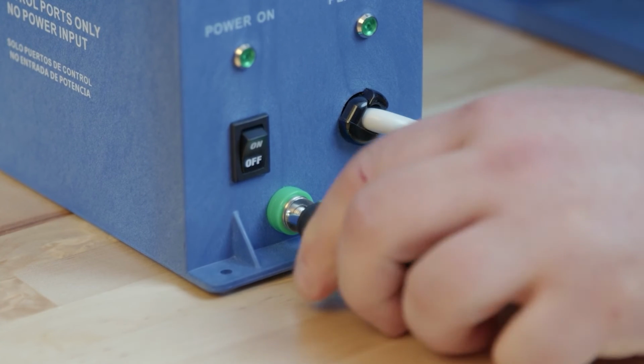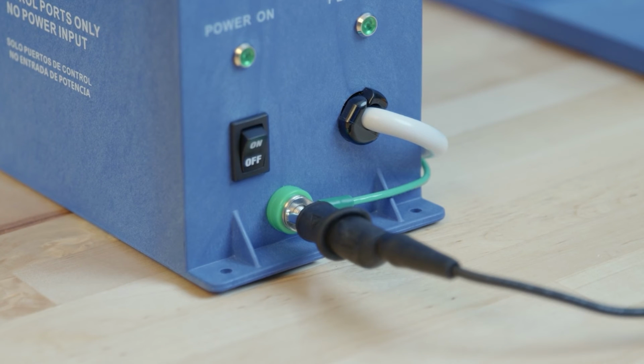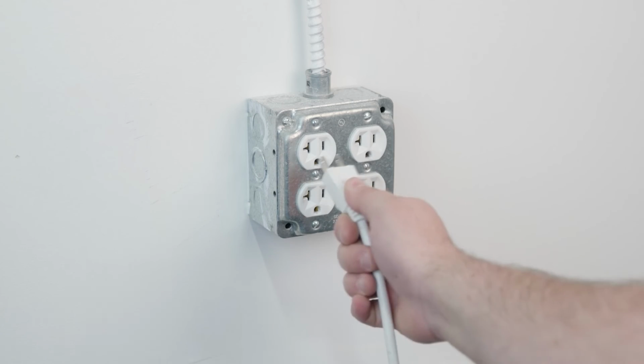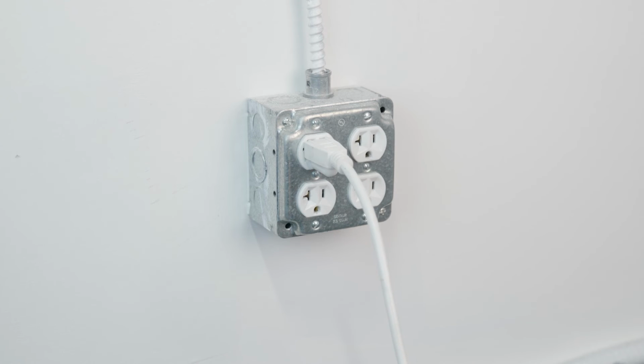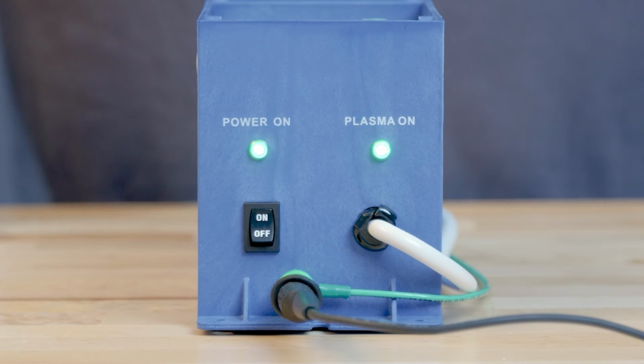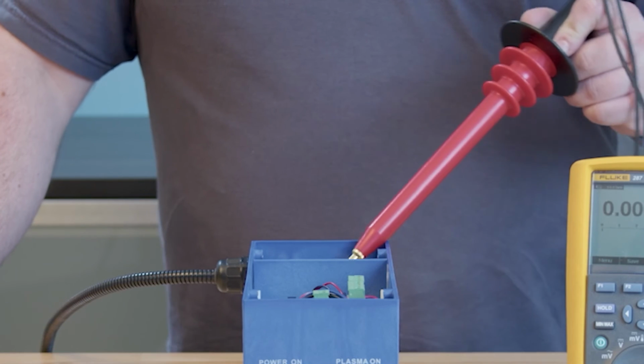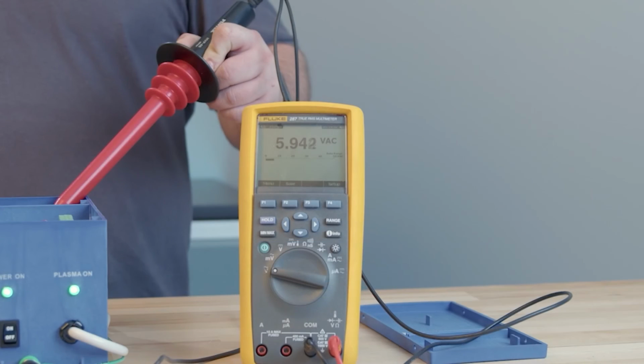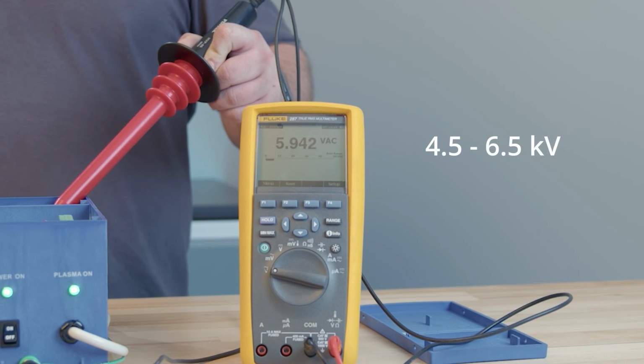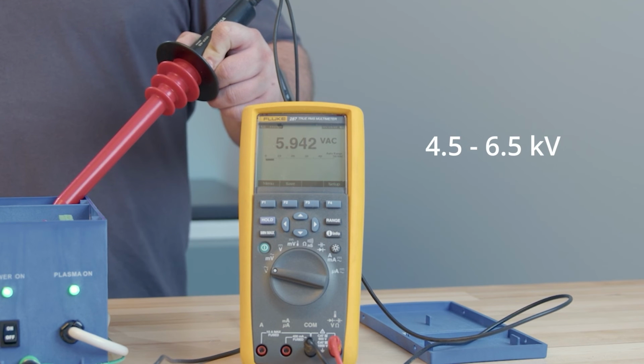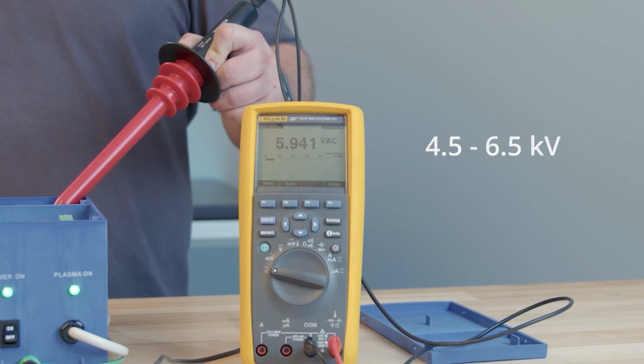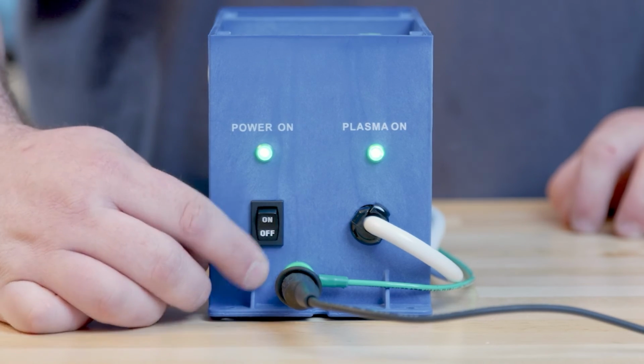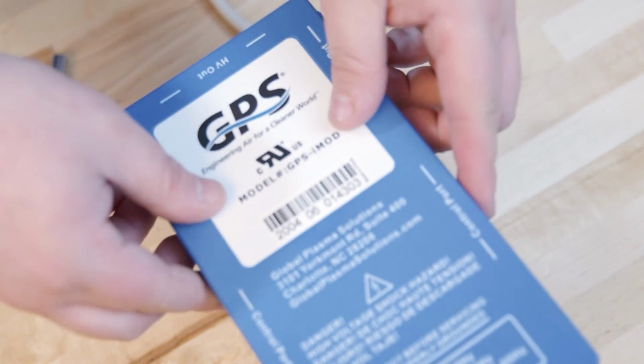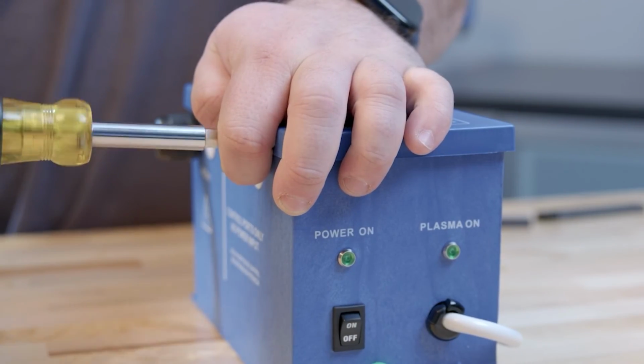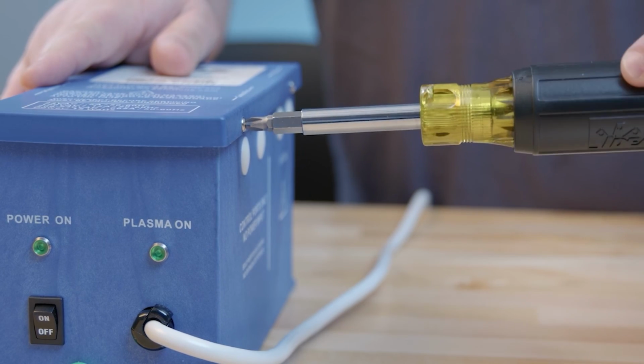If you have a high voltage probe, attach the probe's grounding clamp to the grounding lug. Return input power to the power supply. Power on the device. Place the voltage probe on the high voltage post. Verify the voltage is in the optimal 4.5 to 6.5 kV range. Power off the device. Place the lid back onto the power supply and secure with 4 machine screws.